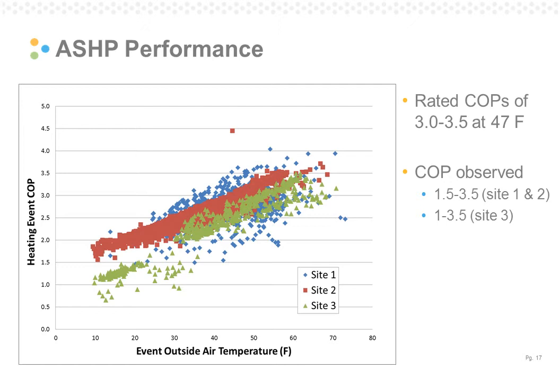Next, we'll take a look at the heating event COPs just for the air source heat pump. So on the x-axis, again, we have the heating event outside air temperature, and the y-axis is the heating event COP. The red data is the data for Site 2, which you actually saw on the previous slide. That's the orange data. The heating event COPs for Site 1 for the air source heat pump have a greater spread than they do at Site 2, but it really follows very closely with Site 2, and actually some of it is hidden, especially down in the 10, 20, 30 degree range. A lot of the data from Site 1 is hidden by Site 2.